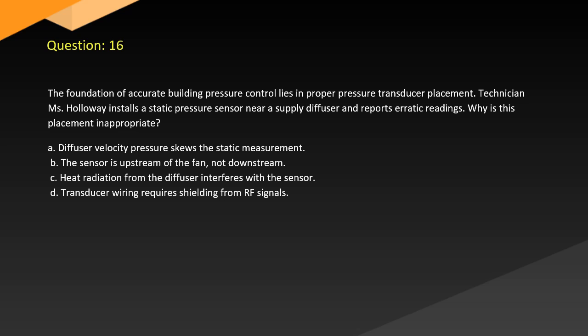Question 16. The foundation of accurate building pressure control lies in proper pressure transducer placement. Technician Holloway installs a static pressure sensor near a supply diffuser and reports erratic readings. Why is this placement inappropriate? A. Diffuser velocity pressure skews the static measurement. B. The sensor is upstream of the fan, not downstream. C. Heat radiation from the diffuser interferes with the sensor. D. Transducer wiring requires shielding from RF signals.